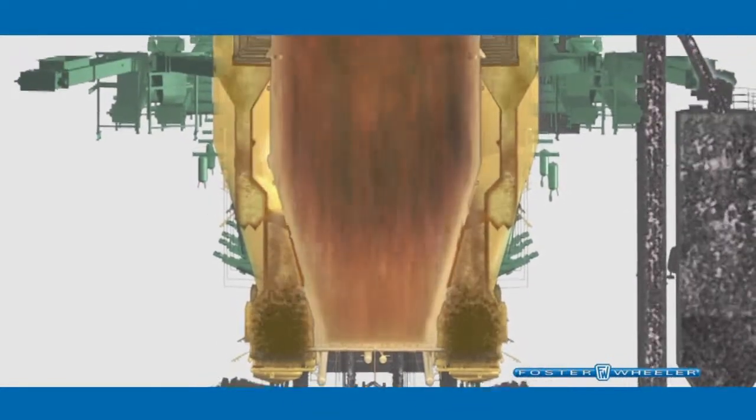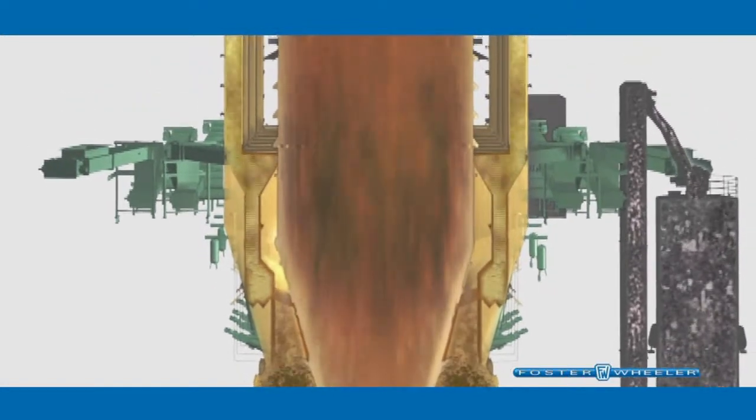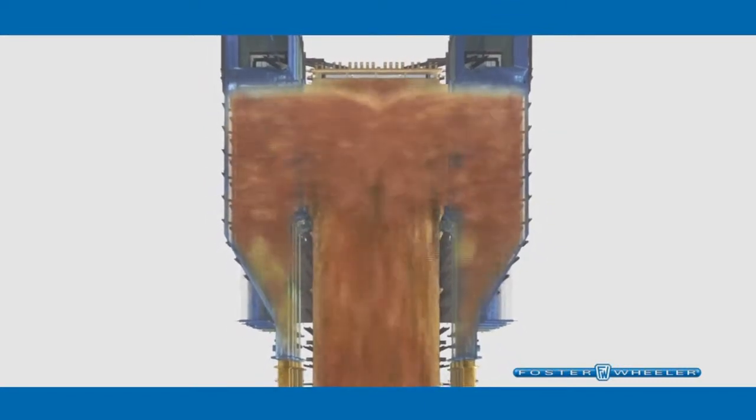The particles eventually reach the top of the furnace and then pass through compact solid separators that capture and return most of them back to the furnace. The compact separators are an advanced design feature of Foster Wheeler's CFB technology, which are made up of steam-cooled panels that are fully integrated with the furnace to form a single monolithic structure.